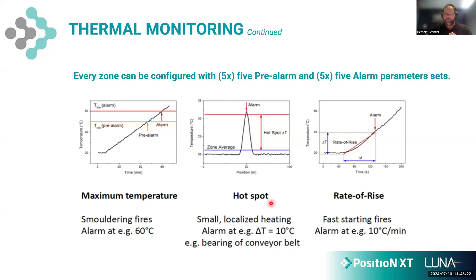But the most important is that for every area of interest along that entire conveyance system, head, tail, take up, drive, even the electrical infrastructure driving it, we can set up 5 unique pre-alarm and 5 unique alarm parameter sets for maximum temperature, for a hotspot along the conveyor, and 3 delta T's, the rate of rise in temperatures, so that we can very early and accurately pick up radiant heat from a pulley, from a roller, from frictional heat from the belt against the structure, or any external event to the belt.